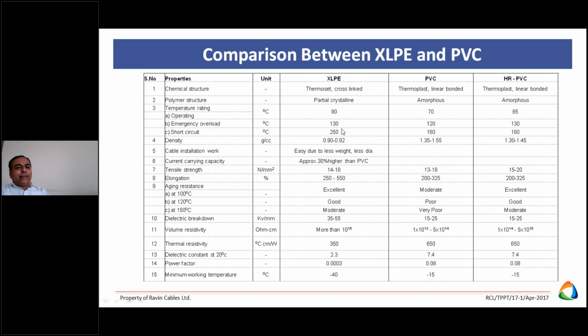Short circuit temperatures are better in XLPE: 250 degrees centigrade versus 160 degrees centigrade. So continuous current rating will be higher in case of XLPE cables. Almost 30% higher current ratings in case of XLPE cable with the same cross-section area of conductor.